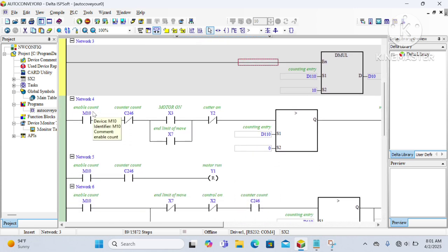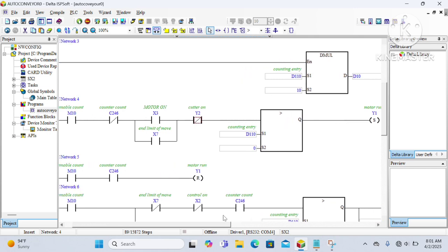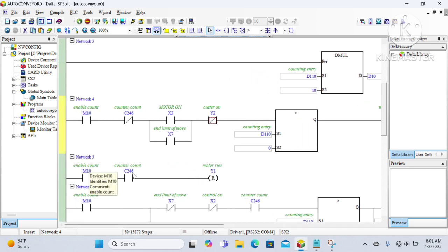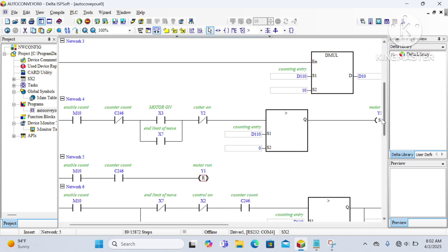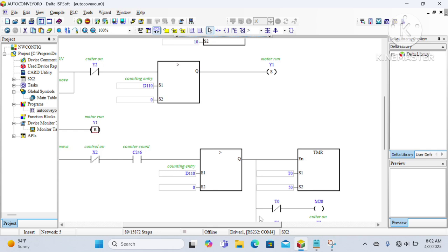In the next step you can see the operation for activation of Y1, which is for the gear motor. This gear motor output enables after pressing the X3 switch, and there is a condition which disables the output at the zero position of the counter. In the next step we reset the gear motor — whenever we need to cut the pipe, the gear motor is reset.